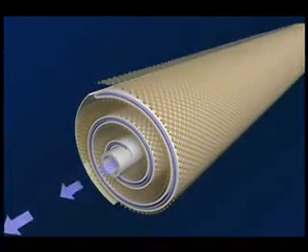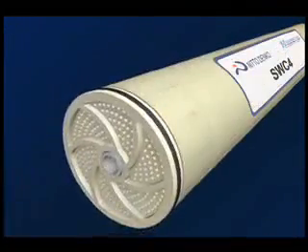Clean water, or permeate, passes through the membrane surface into the permeate channel and then flows in a spiral direction to the center of the element and is collected into the core tube.